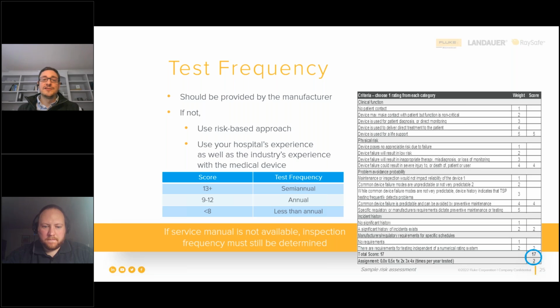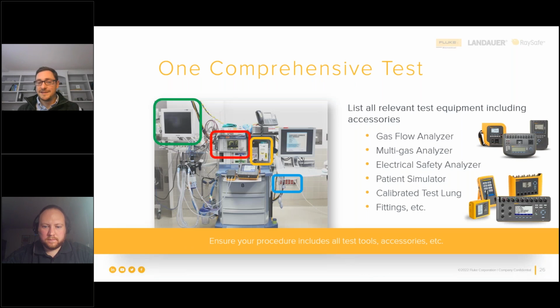And the other part is make sure that your test is comprehensive. You want to make sure that you do one test that covers the whole medical device or asset. So on this slide, we have the example of an anesthesia delivery system. It has a patient monitor, has a ventilator, has a vaporizer, and it runs off mains power. So to do the testing, you need a number of medical devices. You need a gas flow analyzer, you need a multi-gas analyzer, you need an electrical safety analyzer, you need a patient simulator, and the list of tools doesn't just involve that. There's probably some accessories and PM kits and things like that that need to be called out as well. So most medical devices are always doing safety and performance, right? So you always need an electrical safety analyzer and some sort of performance analyzer or simulator. So our advice, make sure that you do it all at one time and link the results back to that asset number. That way you have one comprehensive test tying back to that asset.